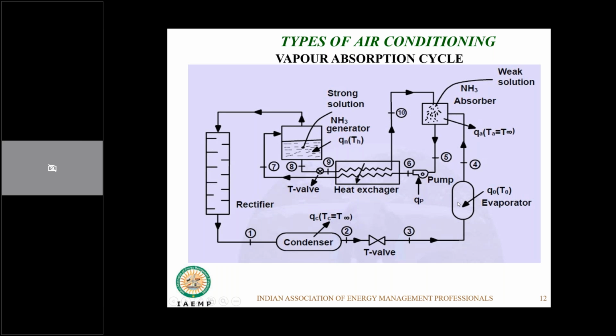Now, let's say here we are talking about the water and ammonia cycle. So the ammonia is the refrigerant here in our case, and water is the absorber. As the liquid ammonia came into the evaporator, it absorbed the heat of evaporation and cooled the water in the vapor absorption chiller. As this ammonia liquid became vapor, it rises and comes into the absorber.